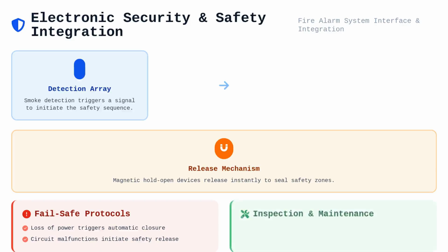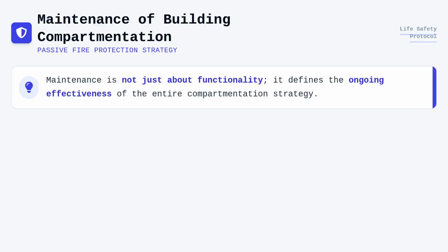Furthermore, field inspection, testing, and maintenance protocols are established to ensure that these mechanical elements do not suffer from degradation over time. Inspectors must verify that clearances remain within the manufacturer's listing and that all door hardware operates smoothly without the need for excessive physical force. Proper maintenance is not just about functionality. It defines the ongoing effectiveness of the entire building compartmentation strategy.